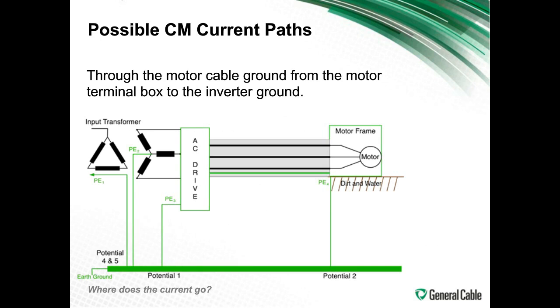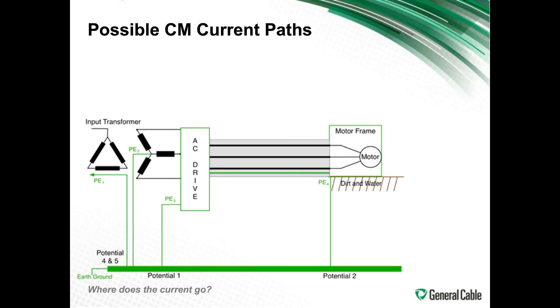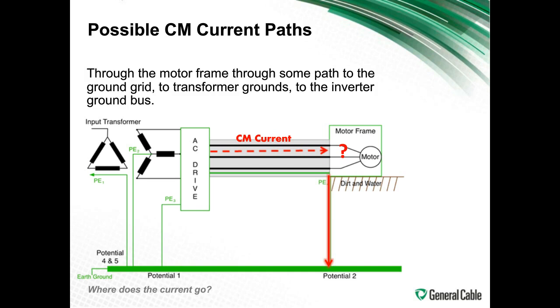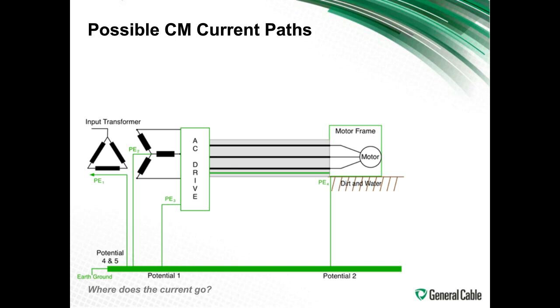So here we've got other possibilities that the current will want to take. You can see many different methods of where the current's going to go. You just don't know, depending on the potential. When you have a potential difference at the motor frame versus the inverter drive frame, look at how the current can flow. It goes back through and goes back into the inverter. So wherever it goes, the current's going to cause trouble. That common mode current will cause trouble.